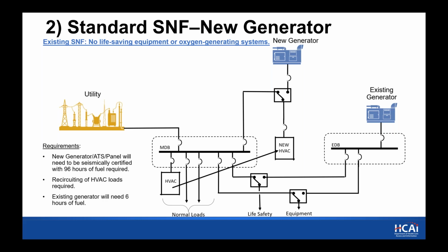So do they have to meet the 96 hours or 128? So the generator needs to be able to run for 96, or whatever the source is, needs to be able to support the facility for 96 hours. NFPA 110 says that basically there's a percentage of the tank that you're not going to be able to get fuel out of. And it also takes into account fuel that would be used during routine testing. So really you just need 96 hours, but NFPA 110 gives a directive for how you size the tanks to get a prescribed hour runtime, and that is where the 133% comes in. So the bill as it's written is looking for 4 days of runtime.